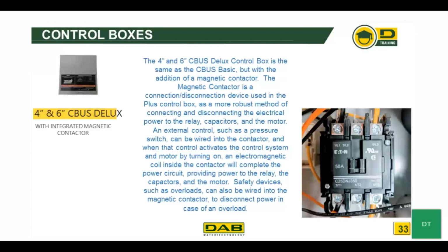The 4-inch CBUS Deluxe control box is the same as the CBUS Basic in many respects, but with the addition of a magnetic contactor. The magnetic contactor is a disconnection connection device used in the Plus or Deluxe control box as a more robust method of connecting and disconnecting the electrical power to the relay, the capacitors, and the motor.